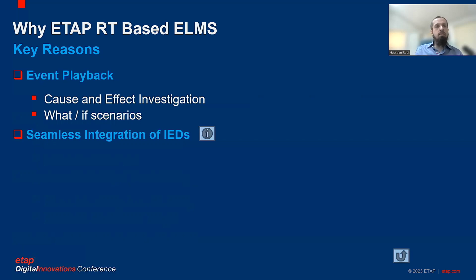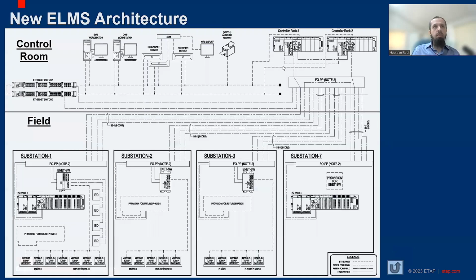And the last but not the least was the seamless integration of IEDs. The system was compatible with all the latest communication protocols, including IEC 61850. So this was the system architecture. You can see the historian servers and the ETAP RT servers along with the workstations. And this is a redundant PLC chassis connected to the remote IO racks in substation 1 and substation 7. And then we have IEDs interfacing with the system at substation 1 over IEC 61850 and at another substation with Modbus TCP. So we actually use two different fiber optic cable networks, independent networks, for data acquisition and load management purposes. Two different communication networks were used.